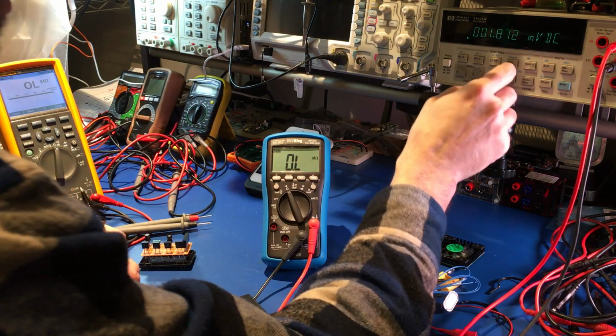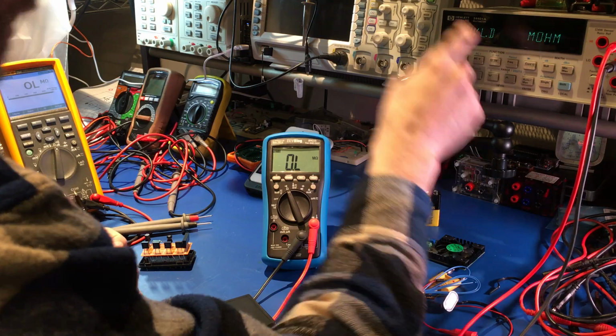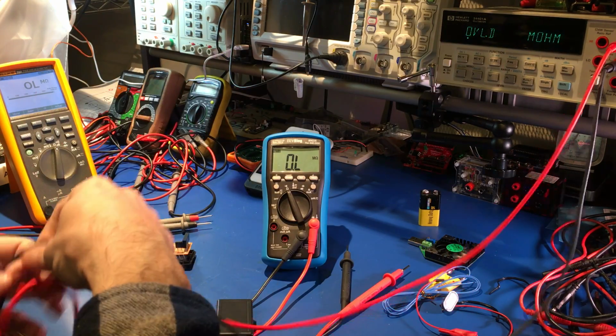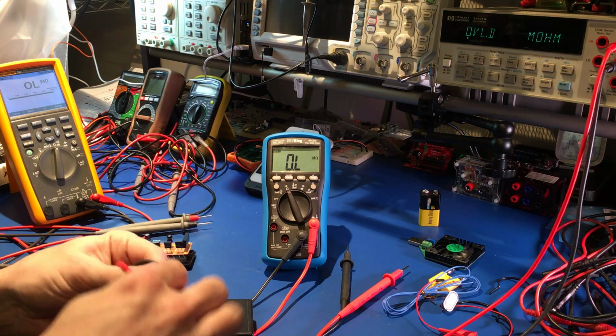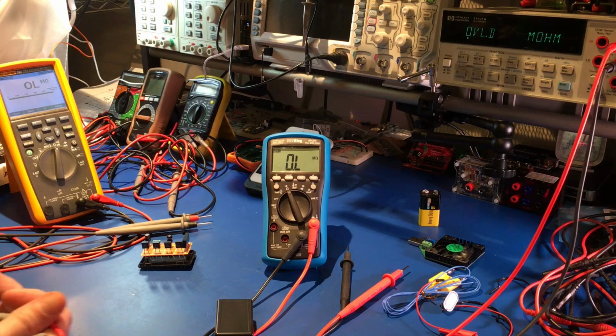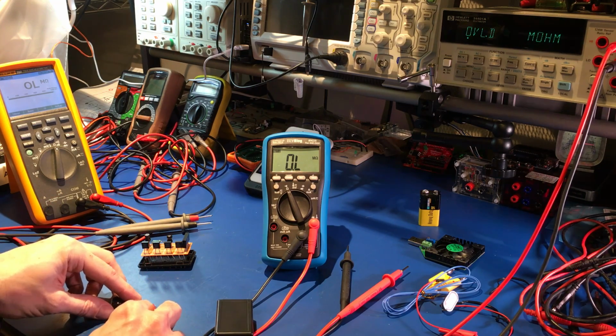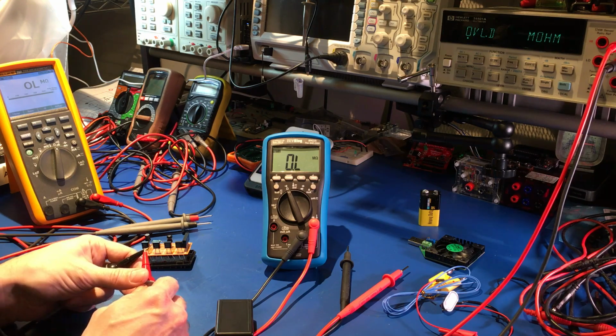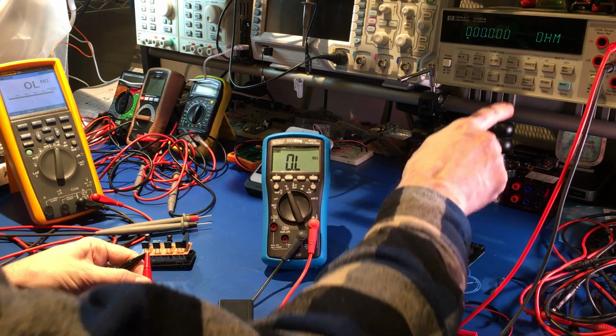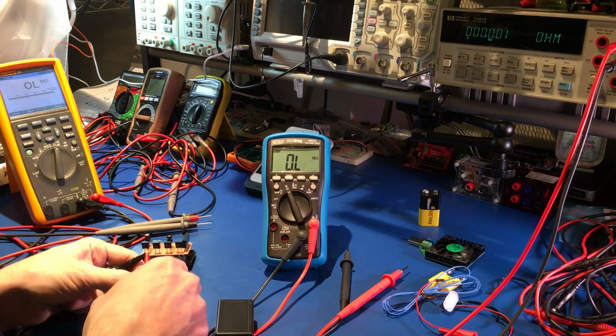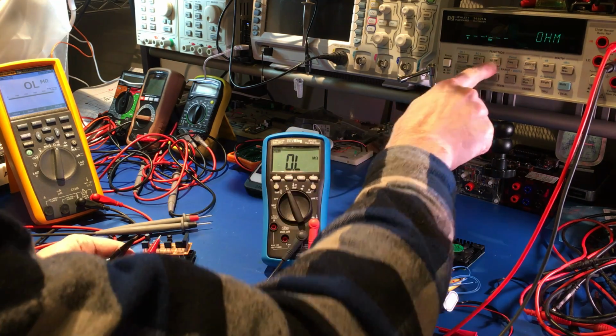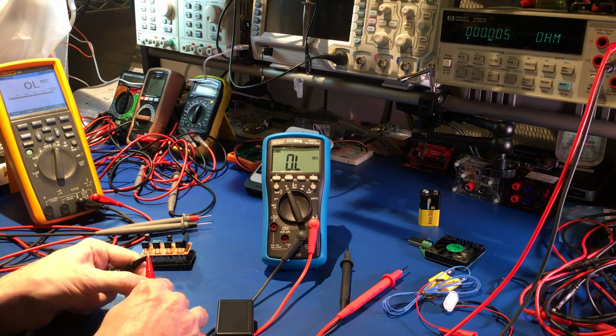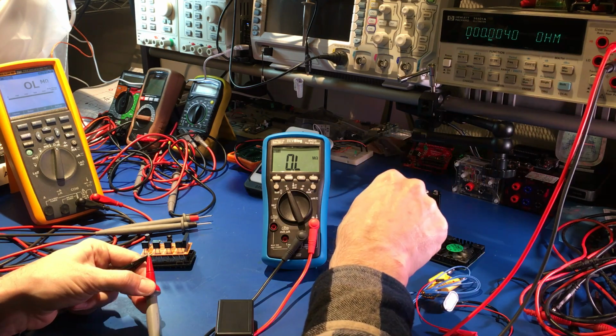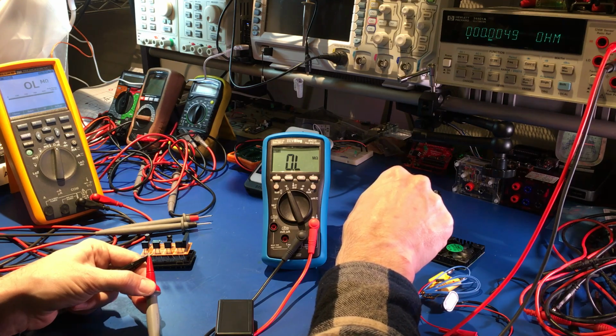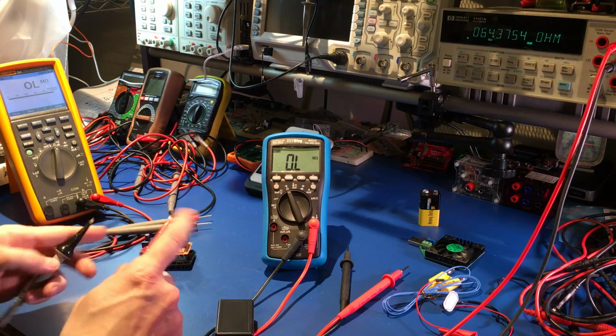We'll use the 2-wire. It does have the 4-wire functionality, but of course I don't have my 4-wire Kelvin set up, and it wouldn't be fair to compare a 4-wire resistance reading to a meter that's only doing 2-wire resistance. But being as this is such an old meter, apparently there's no resistance on my probes. So I guess I don't have to reference anything out or null anything out here, huh? There's a little bit once I go over to 6-digit. We'll null that little bit out.